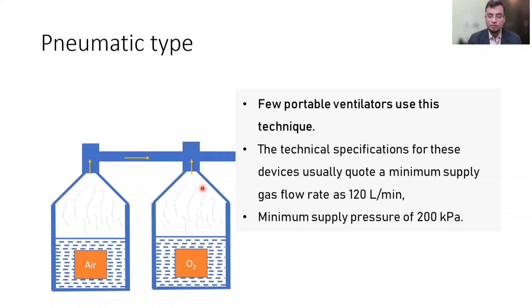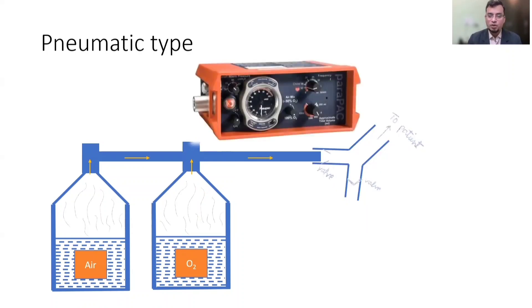In pneumatic-type gas flow generators, gas cylinders are connected to the inspiratory circuit and flow goes to the patient once the inspiratory valves open. Few portable ventilators use this type of technology. The technical specification for these devices usually quotes a minimum supply gas flow rate of about 120 liters per minute or a minimum supply pressure of 200 kPa. The main drawback is that if pressure drops, the power of the ventilator drops.